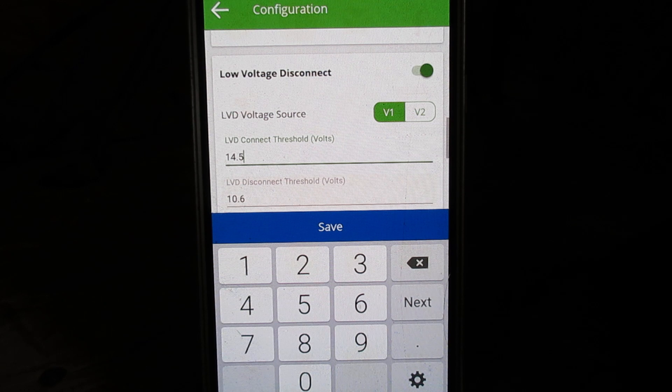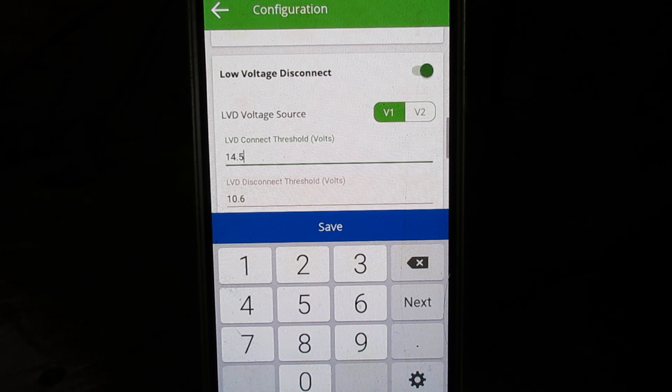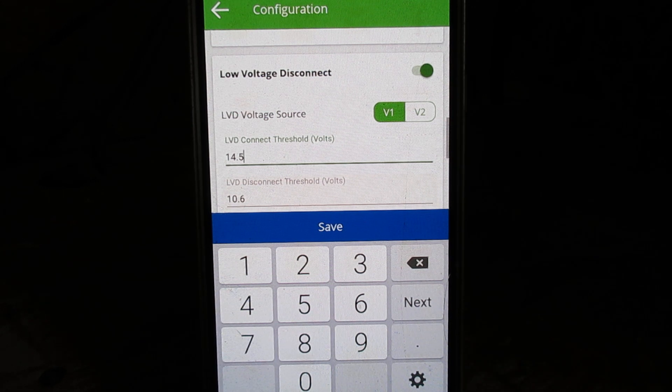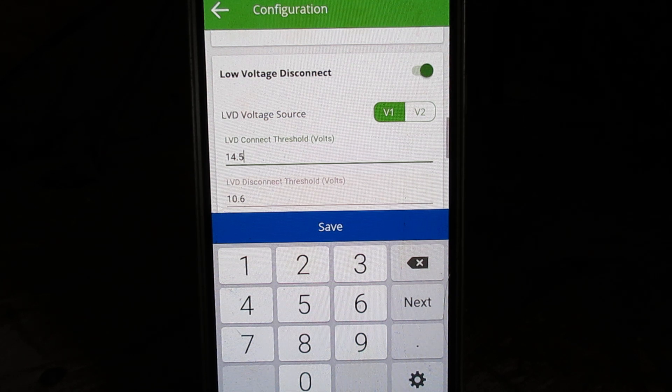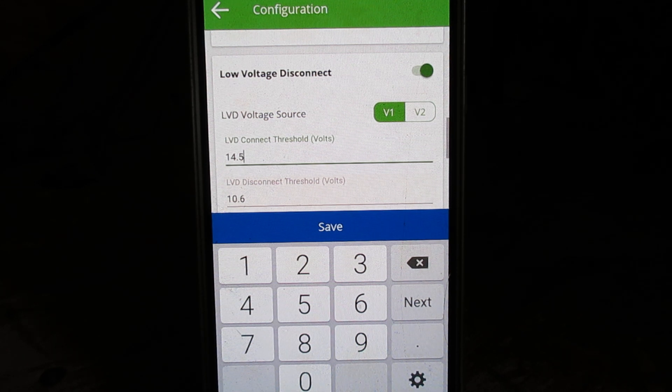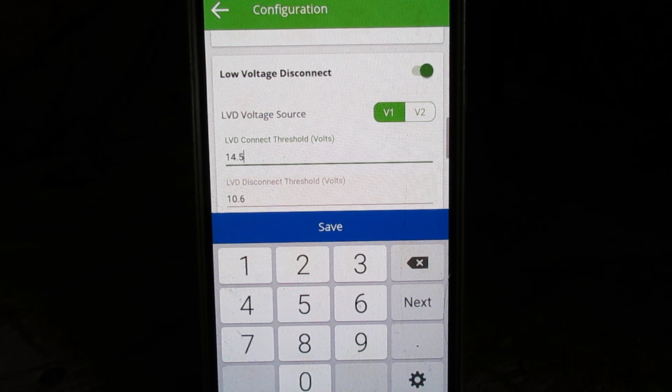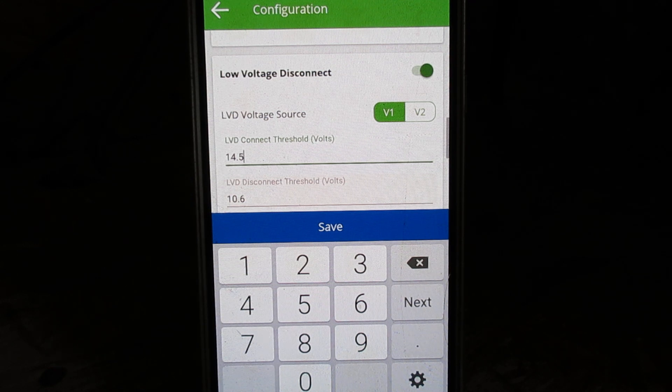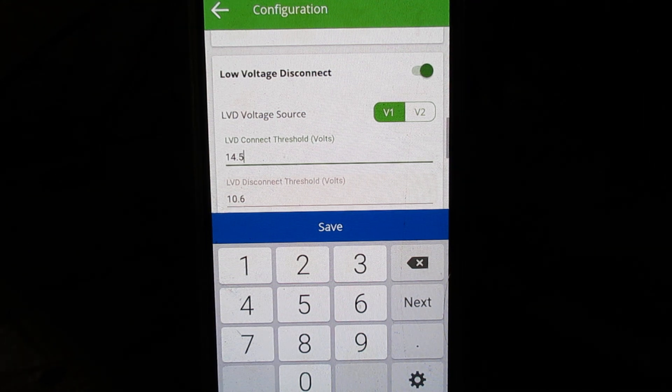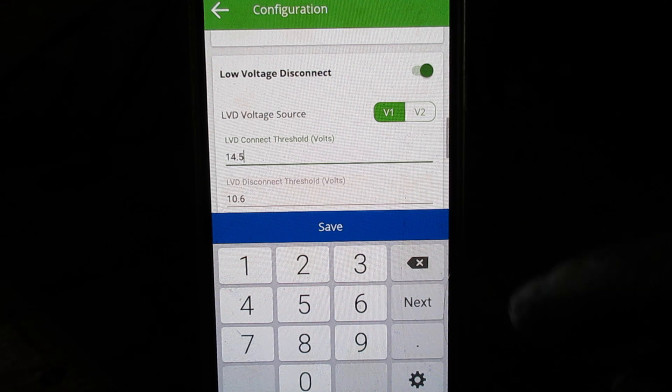Otherwise, if you have it set too high and then the charger goes into its float mode, it'll never reach your high trip point. So it's important that you have that set up correctly.